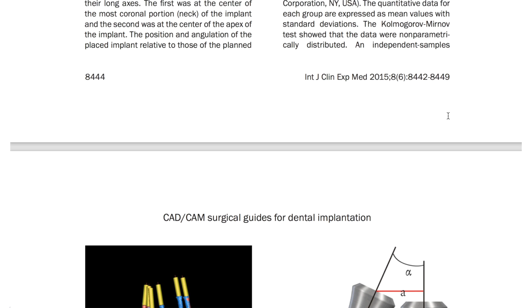Here we see the documentation of the accuracy studies. Standard deviations of 1 to 2 millimeters are measured here, but also the maximal deviations, spanning several millimeters. It is a medical device. The drilling template, as a medical device, must not have any such tolerance values, in my opinion.